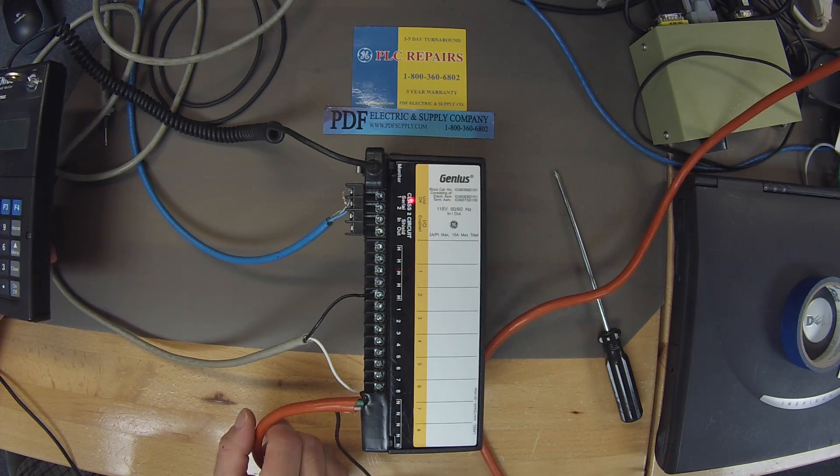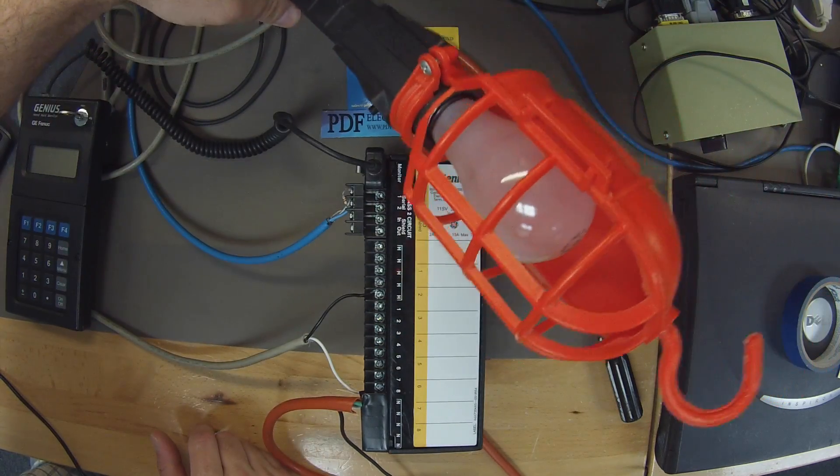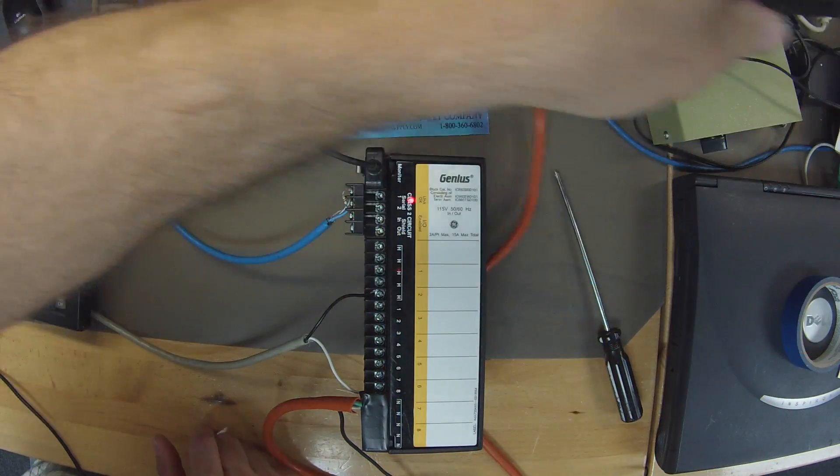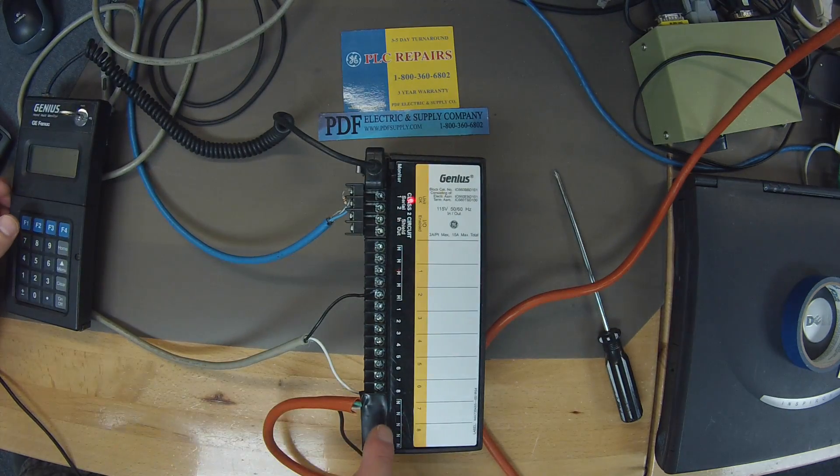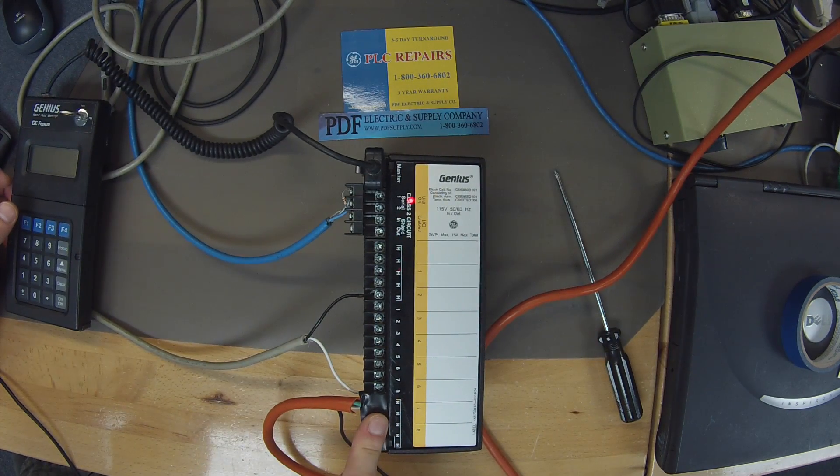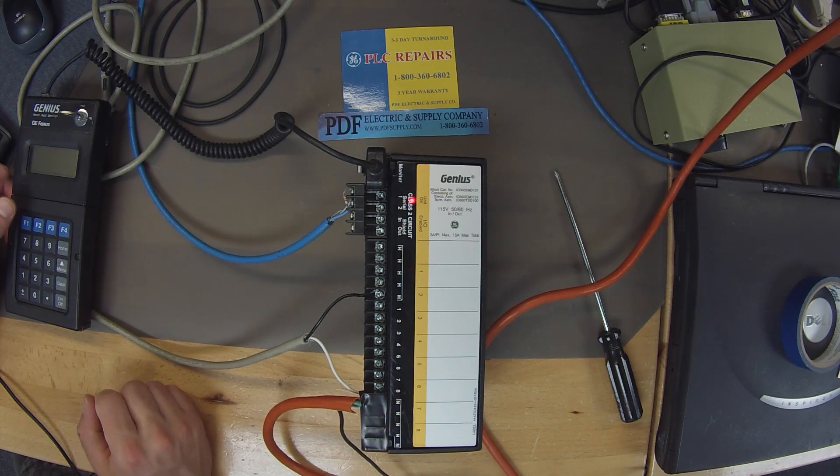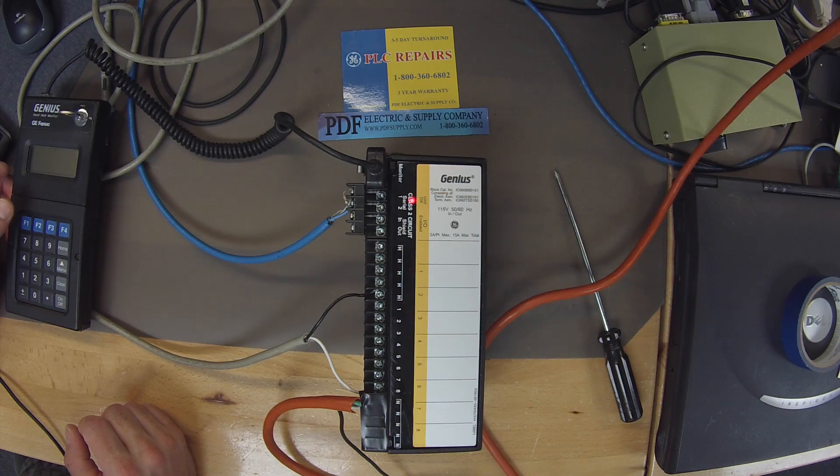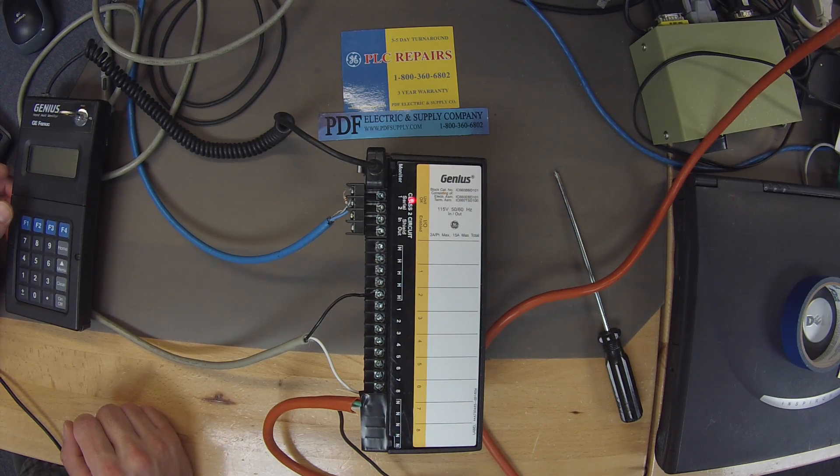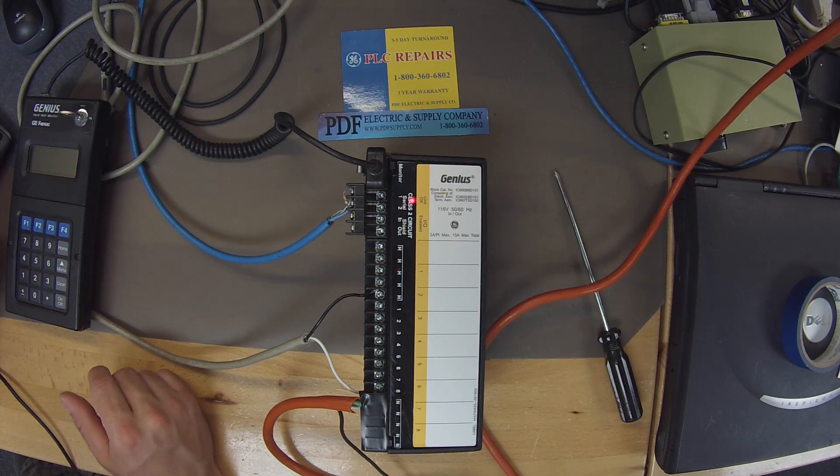Now I also have connected to this a mechanic's drop light. My neutral lead from the drop light is connected right next to my neutral lead from my power input. What I'm going to use that for is to test our outputs. Every time I touch the probe of the hot lead from the light to the inputs, I should be getting a response, basically the light should light up. That's an easy way to test it.